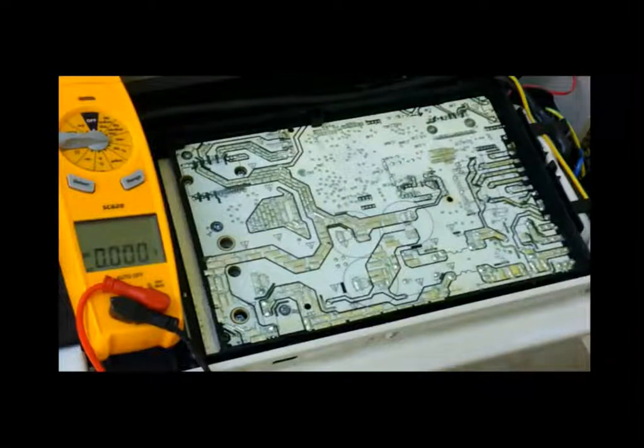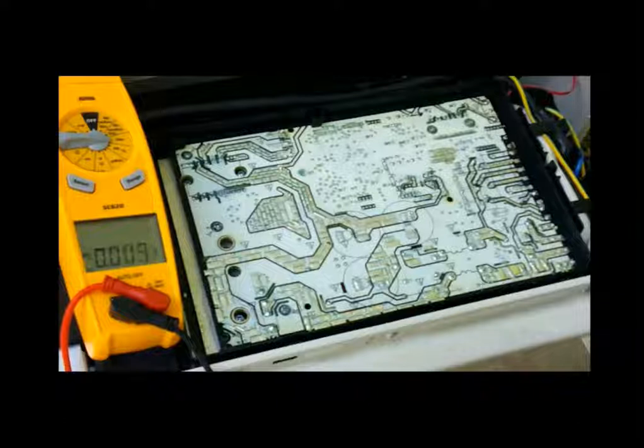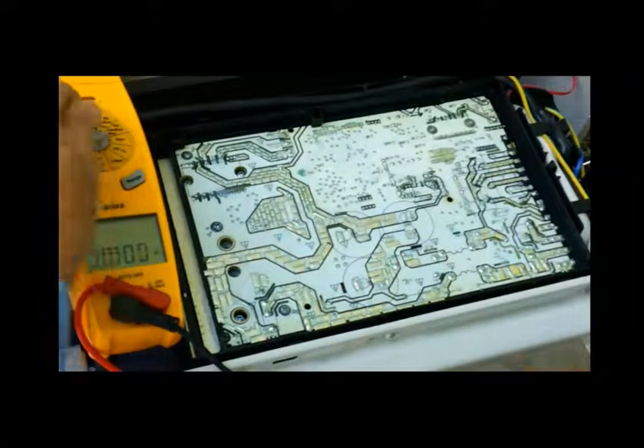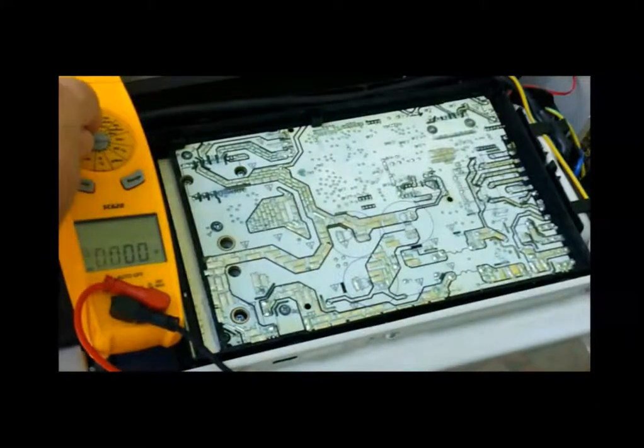Okay, the other thing we need to check on this with the P0 code is your IGBTs. Now that's your insulated gate bipolar transistors. So to check that, we want to make sure we remove power to the unit. We want to wait 15 minutes so that our capacitors can discharge. Now what we're going to do is go ahead and do a test to make sure. So I am checking from L1 to neutral. Being that this is a 115 volt unit, regularly if it's a 230 volt unit, you're going to go from L1 to L2. And obviously, as we can see here, we're going to put this on the AC voltage. We don't have anything.